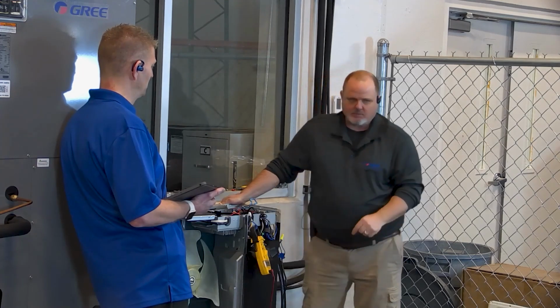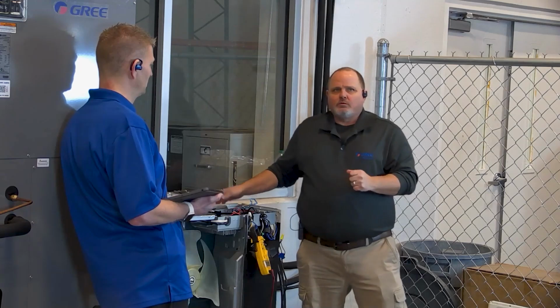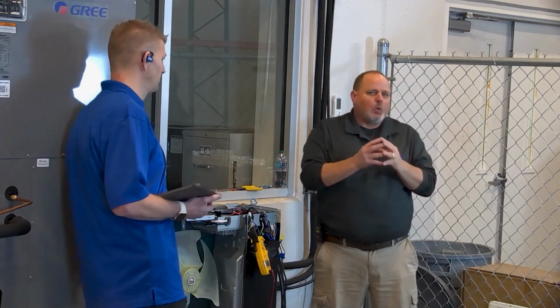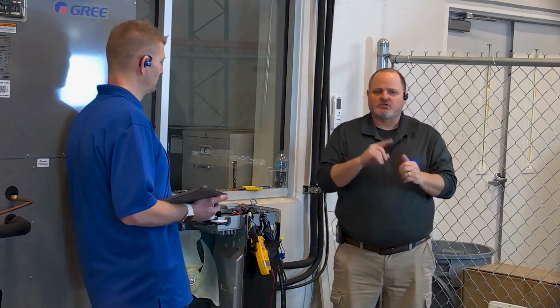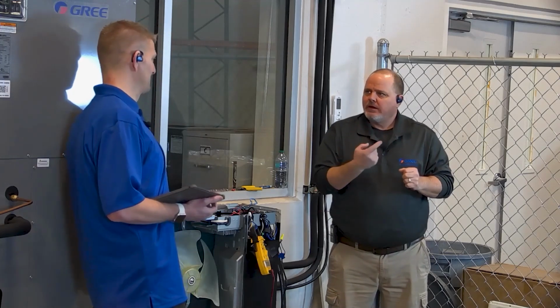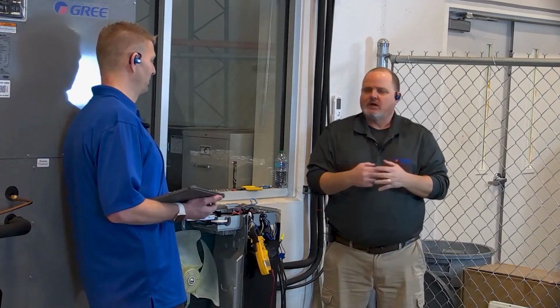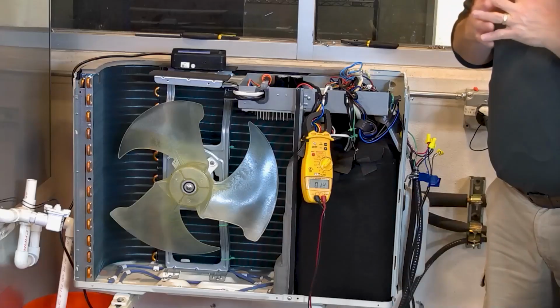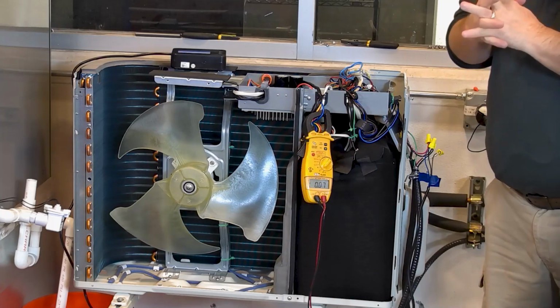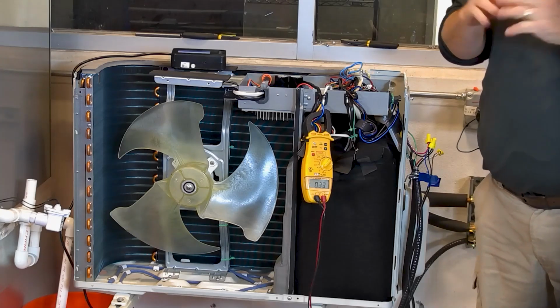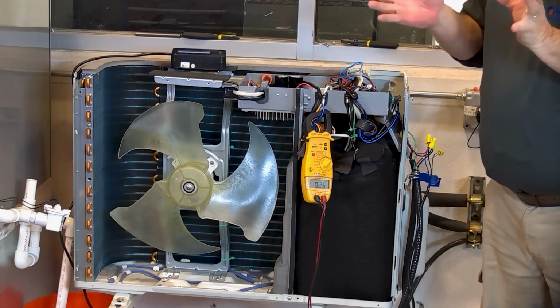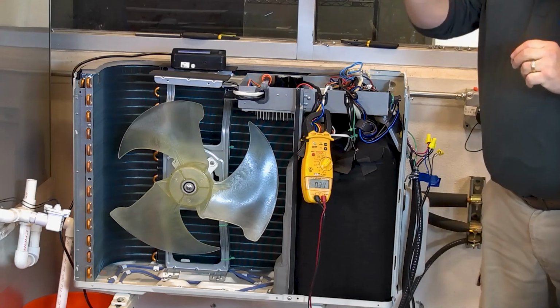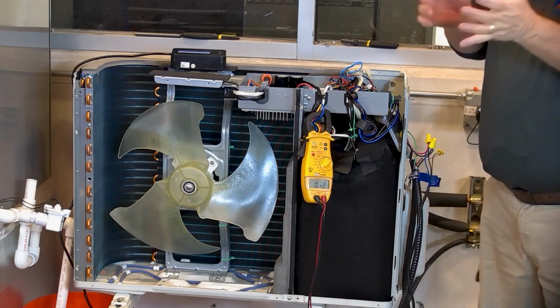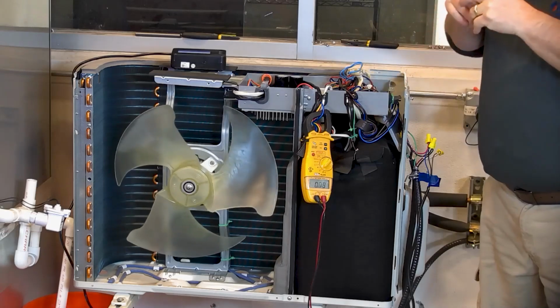to drive this three-phase compressor. So desynchronization, what does that mean? That means the compressor's spinning out of step. It's not in phase. You could have the same thing with a compressor where it won't start because it's single phasing. That's a big term that's always talked about in commercial three-phase compressors, okay? If you only got single-phase power going to a three-phase compressor, that compressor is not going to run because it is quote-unquote single-phasing, okay? Same thing here.